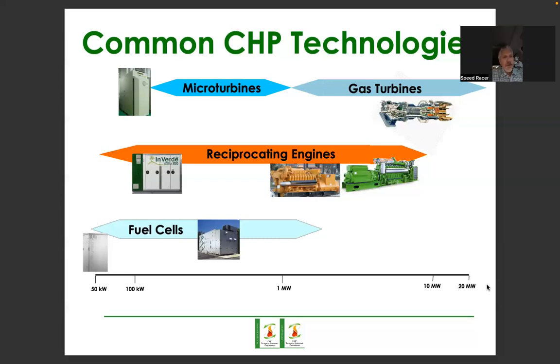You can see the size range goes from the lowest 50 kilowatts up to 10 megawatts, and that's per prime mover. So if you have a 10 megawatt engine and want 50 megawatts of capacity, it's a good model to use five 10-megawatt recip piston engines, or ten 5-megawatt machines, or sometimes even more. The nice thing about putting multiple generator sets in is that you have some built-in redundancy, particularly if your load curve isn't flat. So piston engines are the most common application.